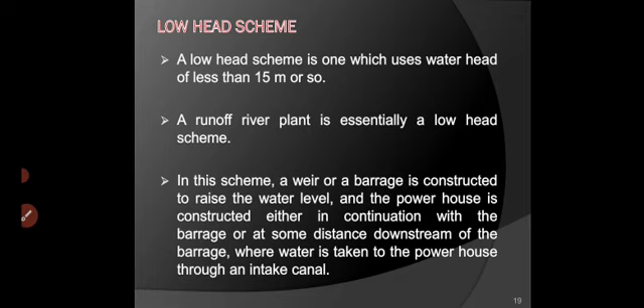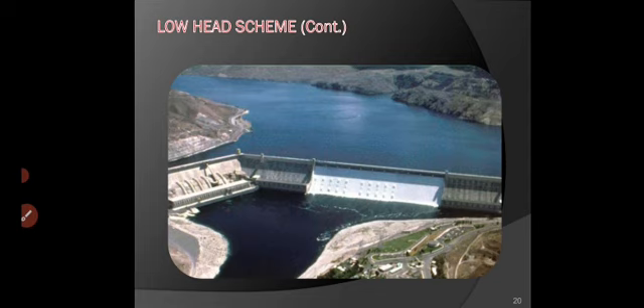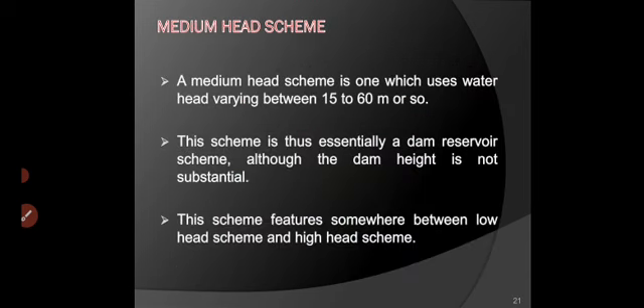In a low head scheme, a large dam is not required. By constructing a weir or barrage, a head of up to 15 meters can be achieved. A barrage is constructed to raise the water level, and the powerhouse is constructed either in continuation with the barrage or at some distance downstream, where water is taken through an intake canal. The low barrage is provided with gates and the powerhouse is constructed nearby. Medium head scheme uses a head between 15 to 60 meters; a dam is required, though the dam height is not substantial. This scheme features characteristics somewhere between low head and high head schemes.